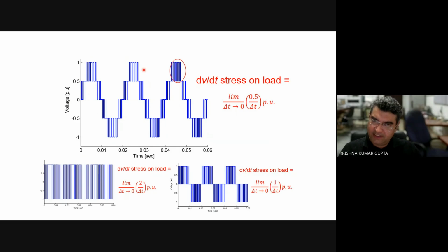Visually, we can see that this is a better imitation of a sinusoidal function. The dV by dt stress on the load is further reduced because this step is only of magnitude 0.5. So compared to a 2-level inverter, this 5-level inverter imposes 1/4 of the dV by dt stress on the load, meaning the lifetime of the load, which happens to be a traction motor in our case, will be more if you use this kind of inverter.